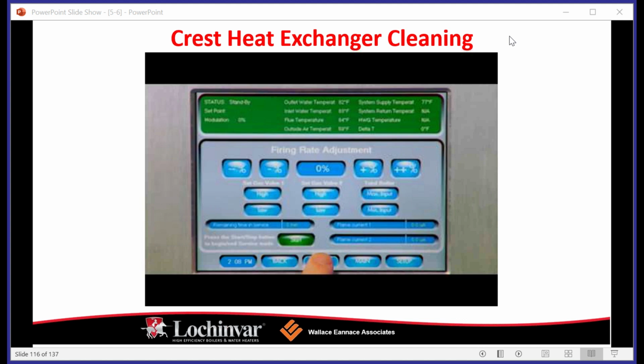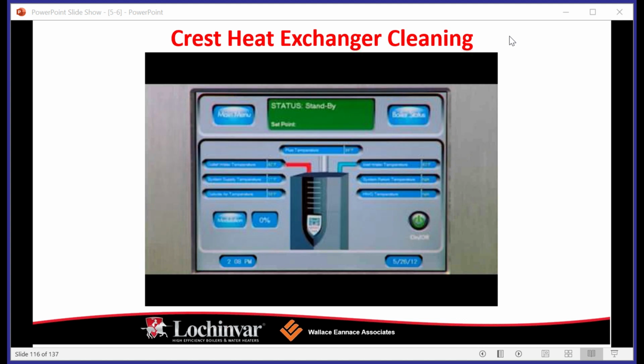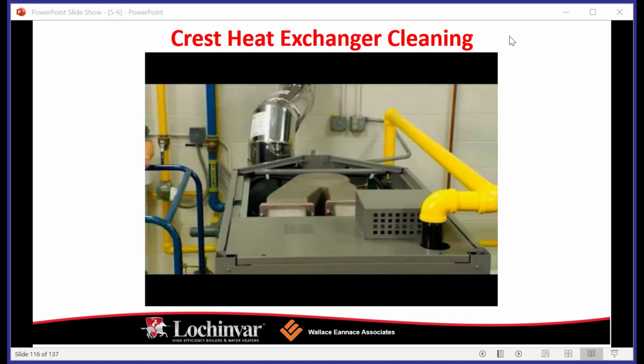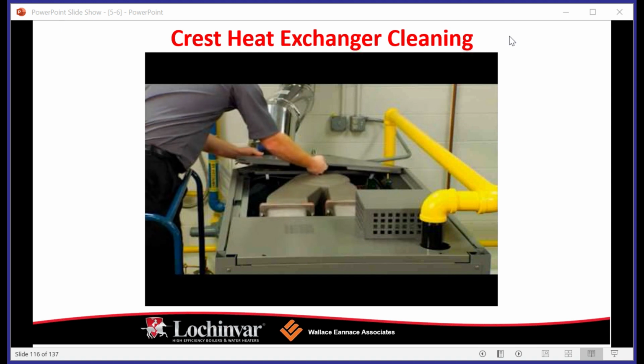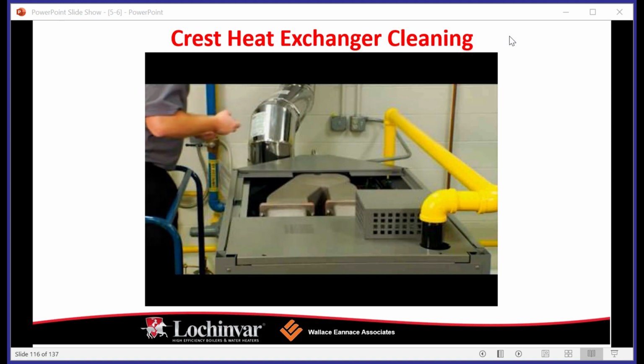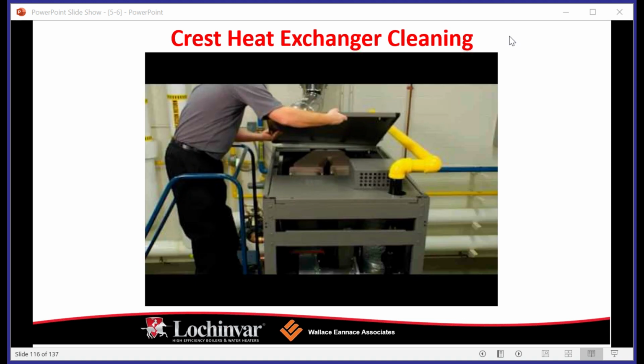Replace the insulation blanket on top of the heat exchanger. Reconnect the wiring from the igniter and flame rods. Reinstall the burner with the burner gasket back into the heat exchanger door.